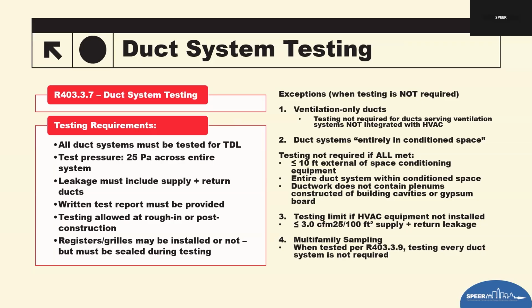Basically, the testing requirements are, first, every duct system must be tested to total duct leakage, TDL, not leakage to outside. We just talked about that. That's new language reinforcing testing the entire system. All the tests have to be performed at 25 pascals across the whole duct system. And the leakage number must include both supply and return. So when a result is entered on a compliance form, it includes both supply and return.